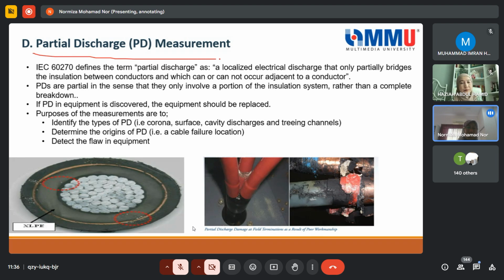Okay, the last one, which is partial discharge, as I mentioned before. Anyway, we come to the end already, so I'll just go very briefly, just to expose you to what partial discharge is. At MMU, we put this topic under testing. For example, you have done all the connections in the substation. Then how do you know that your connection of the cable and everything is intact according to the standard? Because you have to rely on your staff or your worker. So when everything is done, then normally we apply this partial discharge measurement, so that we'll be able to know the health, whether it passed the test or not. So this is part of the testing requirement.